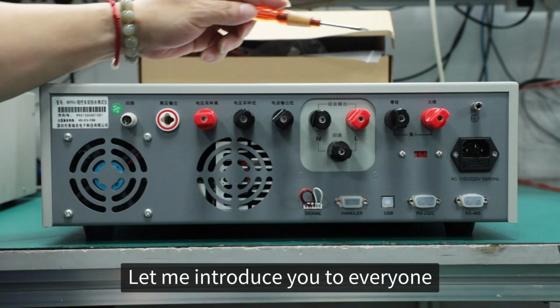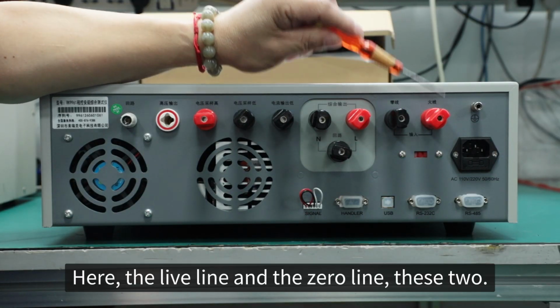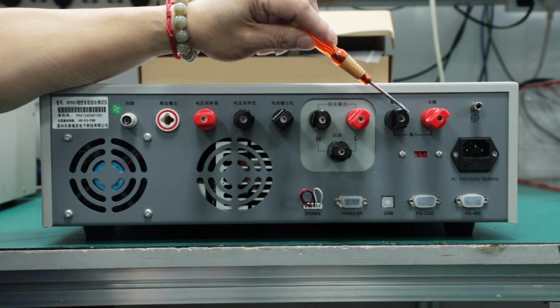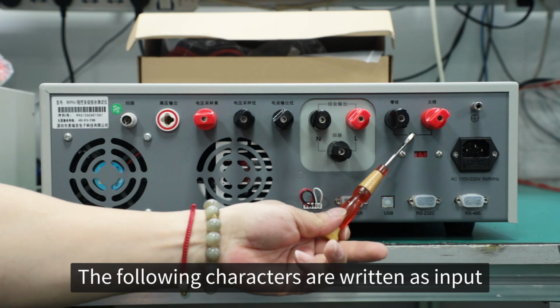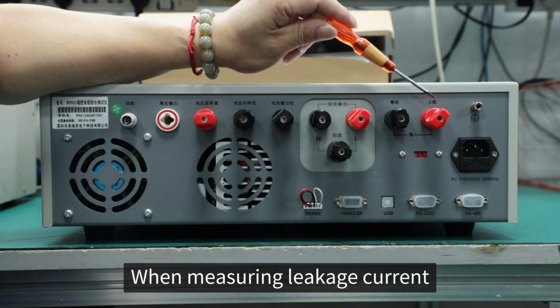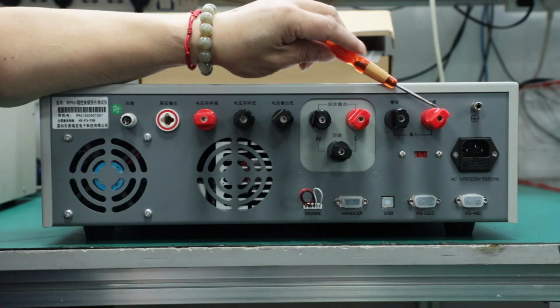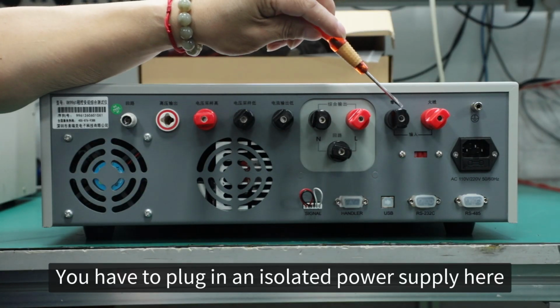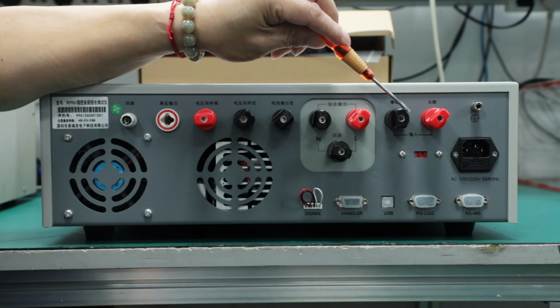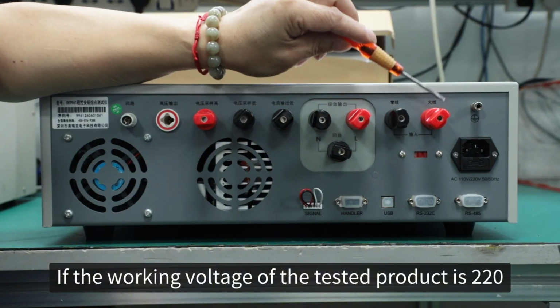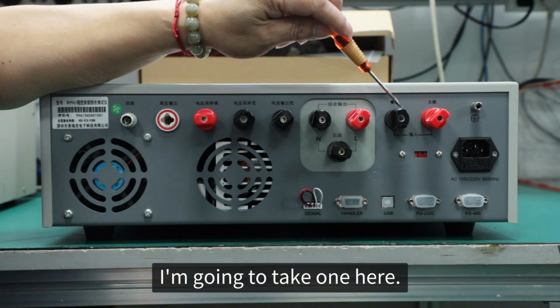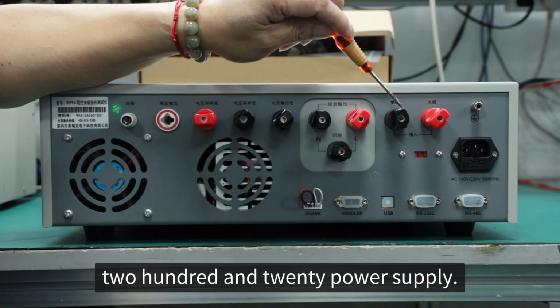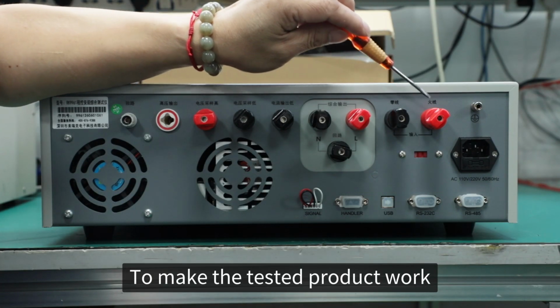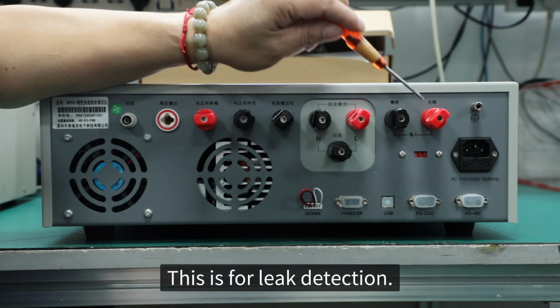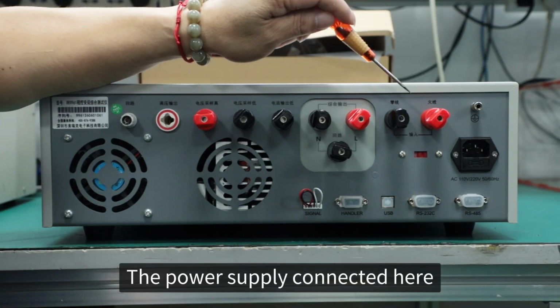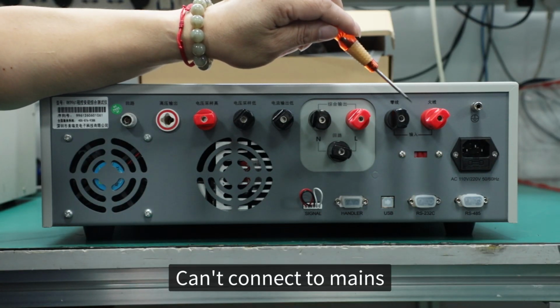Let me introduce them to everyone. Here, the live line and the zero line, these 2. The following characters are written as input. What does this input represent? When measuring leakage current, you have to plug in an isolated power supply here. If the working voltage of the tested product is 220, I'm going to take a 220 power supply here to make the tested product work. This is for leakage detection. The power supply connected here must be isolated; it can't connect to mains.